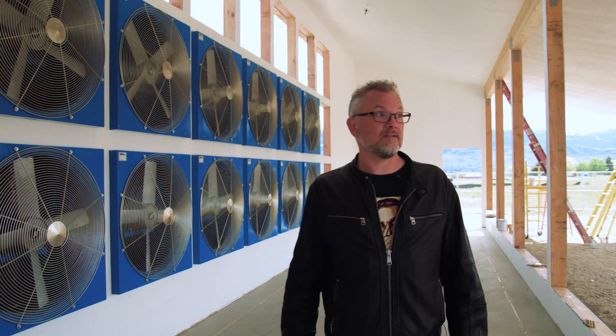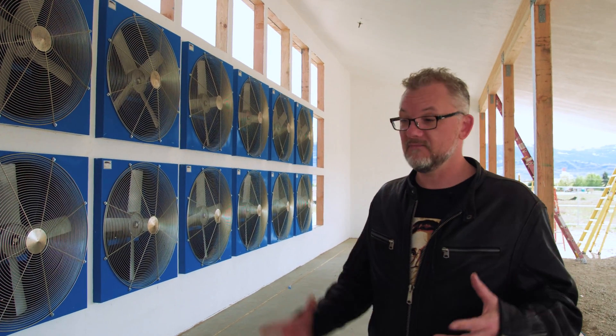It's going to be amazing standing inside here when the air is just rushing through all these fans — it's going to feel like you're being pulled towards them. That's what it takes to do an air-cooled 1.7-megawatt gigapod. One thing worth talking about is cooling — why not just use a ton of air conditioning like traditional data centers do? Why not have rows and rows of AC units along a gigapod? First of all, that costs a ton of money — we could easily spend 30 to 50 percent more on air conditioning units for each gigapod, and that cost ends up coming to our customers.